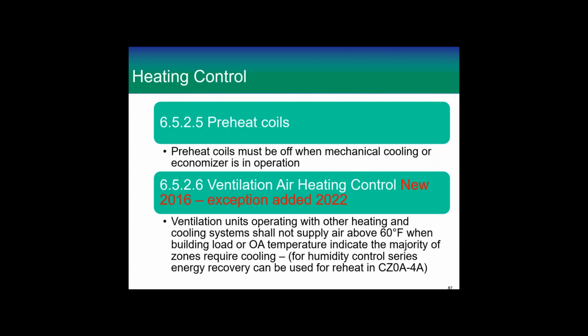All right, so what we're saying here is if you do have a DOAS supplying air directly to the room, we don't allow you to reheat it. So you cooled it down to 55, say, or maybe 53, to get rid of all the humidity in it, because you had a lot of humidity in that outside air. We don't want you to reheat it, because if you're supplying a small amount of the total air to that room, you can find a place to blow it where it won't blow directly on a person, maybe. It will help if the building is in air conditioning mode anyway. We don't want you to throw away that cold air. We want you to use it instead of using the main system to cool that same air.